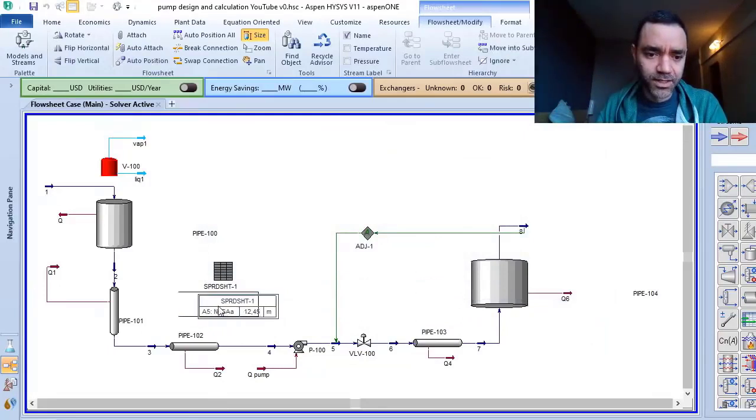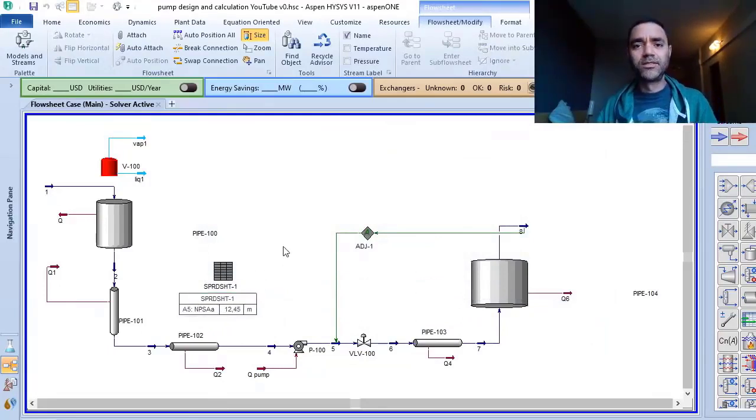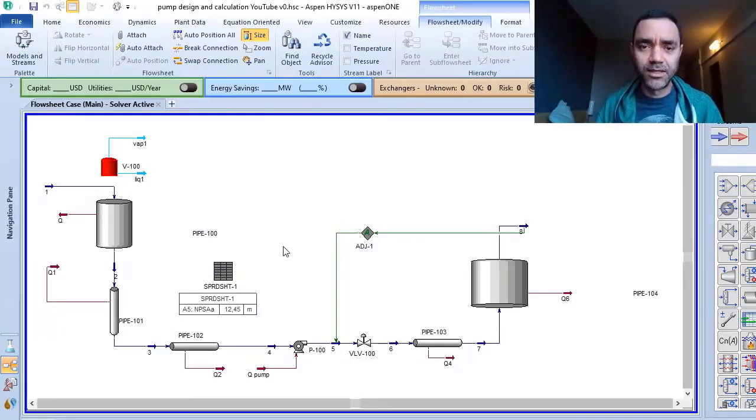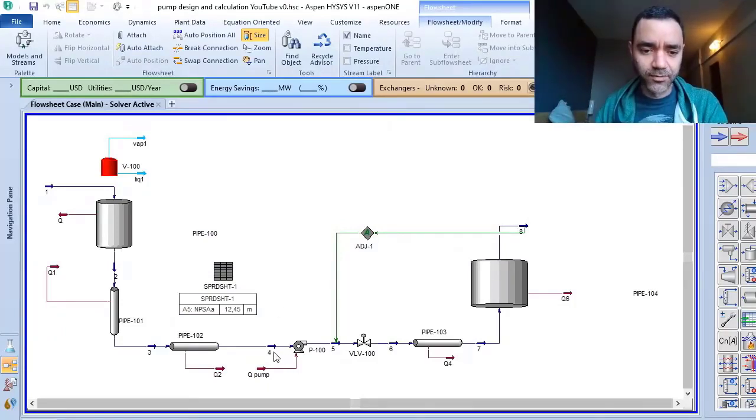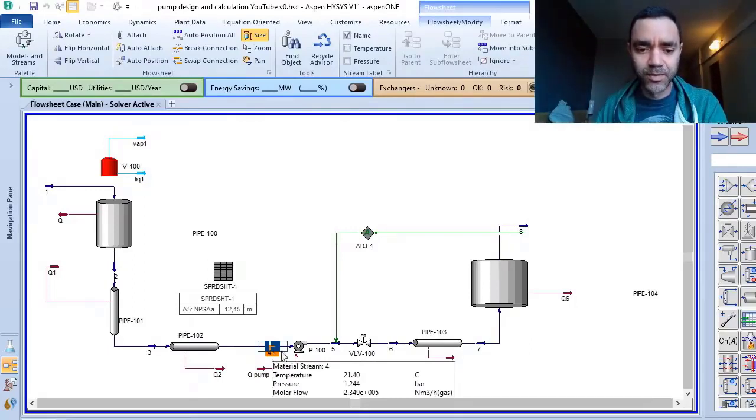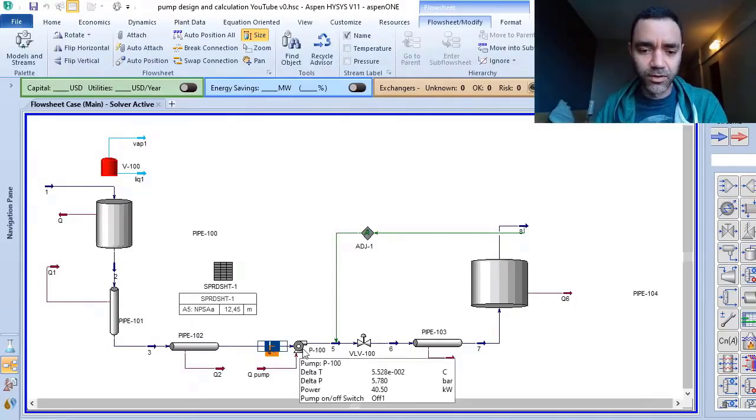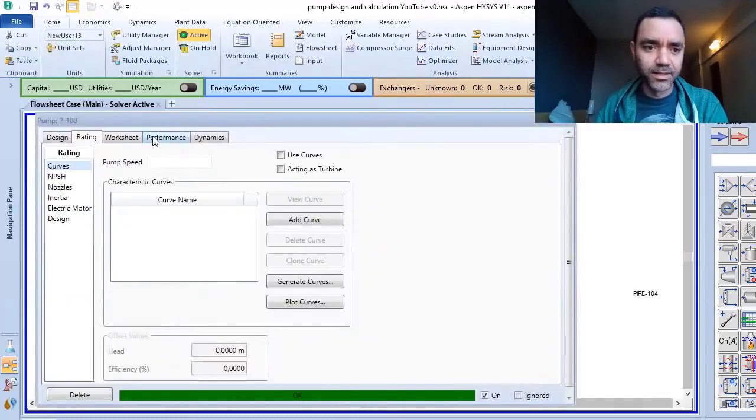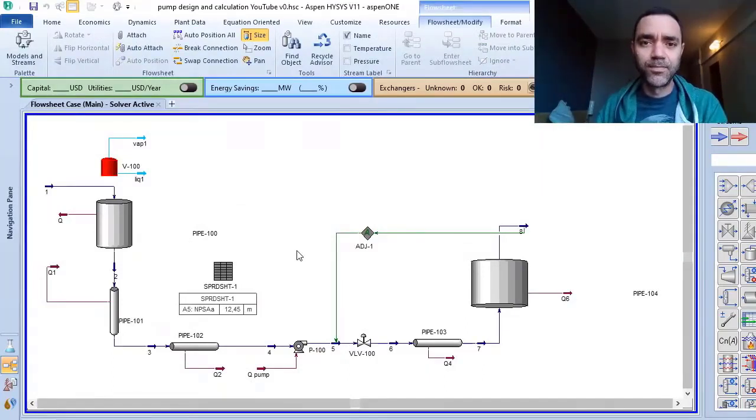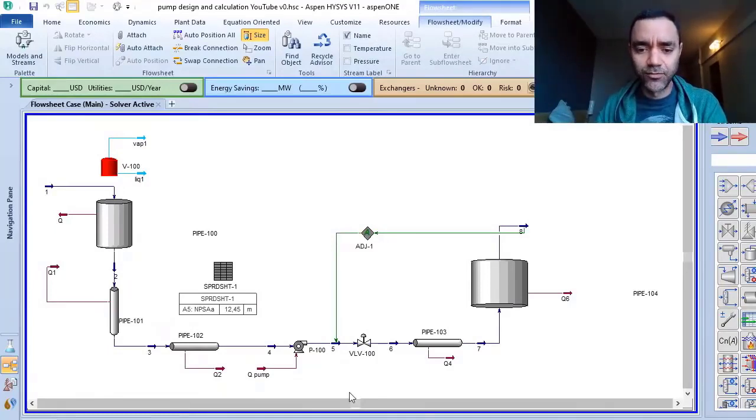So with this, you have everything that you need to do a quotation of a new pump to your plant design. You have the flow, you have the process conditions at the inlet of the pump, you have calculated the pressure head, you have the NPSH available, and the only thing that you need now is a document to fill all of this information.